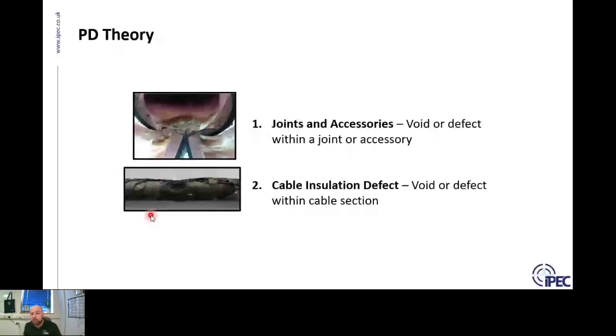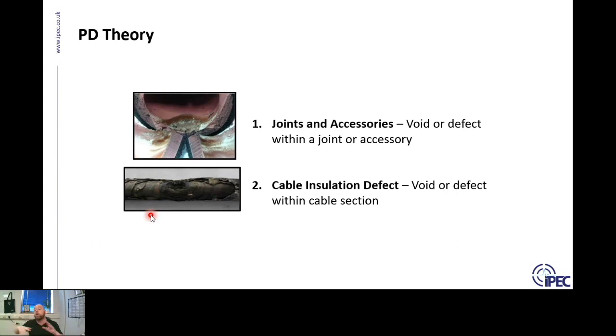The weakest points are the cable joints, so the majority of failures will be found inside cable joints — and also terminations. We often refer to termination PD as switchgear PD because it is inside the switchgear, but it's still part of your cable network. So joints, accessories, and terminations — that's where we're looking to find partial discharge activity.